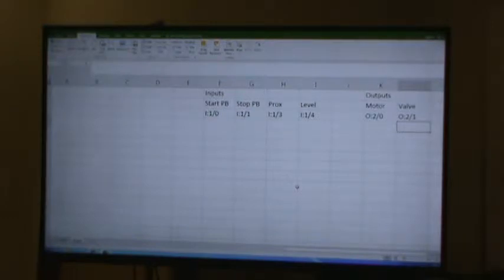So I'm going to simplify the state machine by simply creating all of these state bits, but I'll have all individual state bits. Let me explain. So for the stop state, for example, I will set aside a bit at address 0 in memory, in the bit's memory, that will indicate that I'm in the stop state. Basically, if this bit is on, I'm in the stop state. If it's off, I'm not in the stop state. Okay? So I'm going to abbreviate this as B0. That's just what I'm going to call it temporarily. I'm going to give it a name.